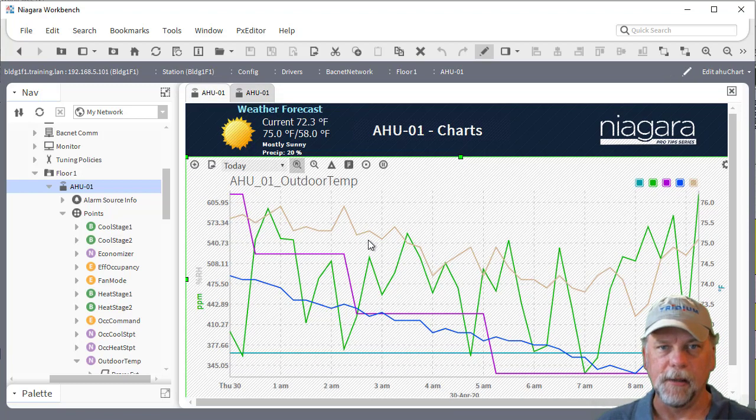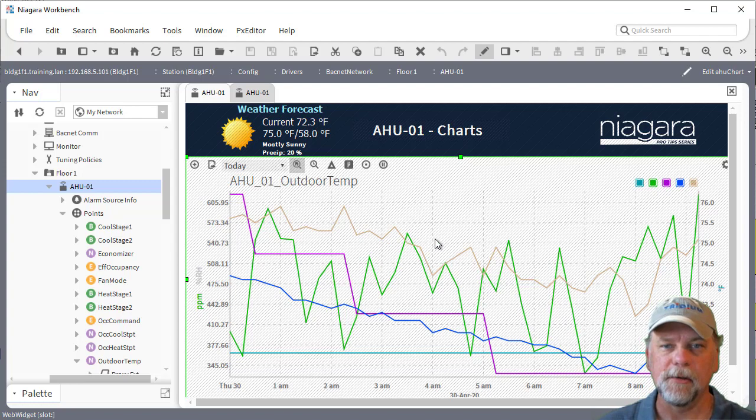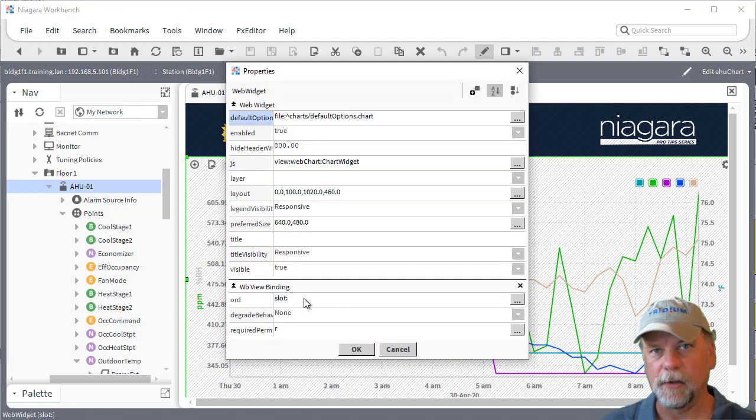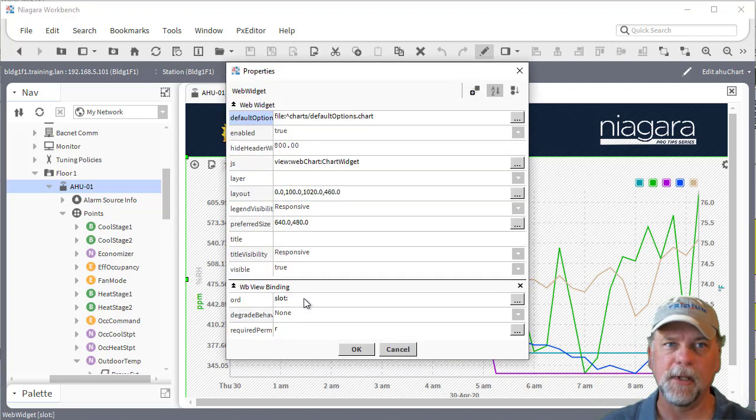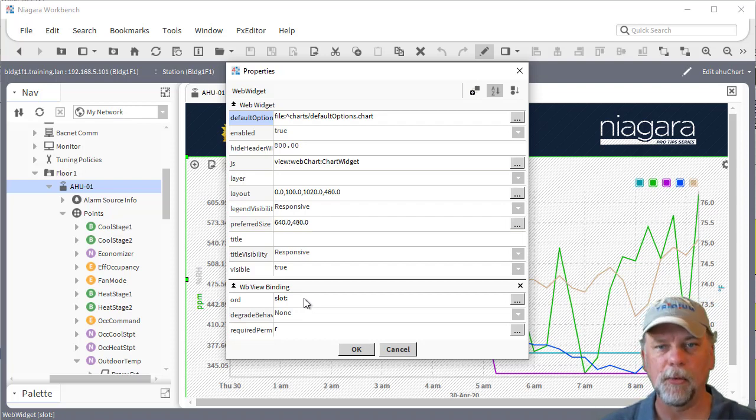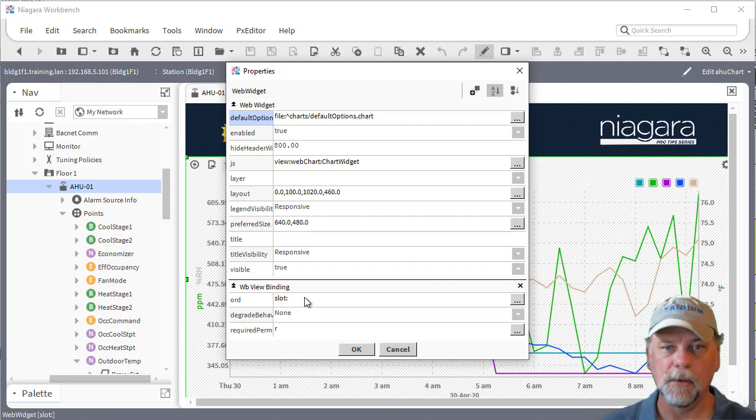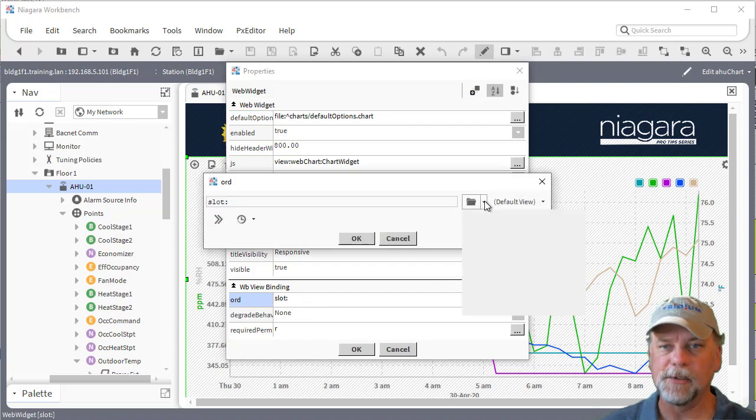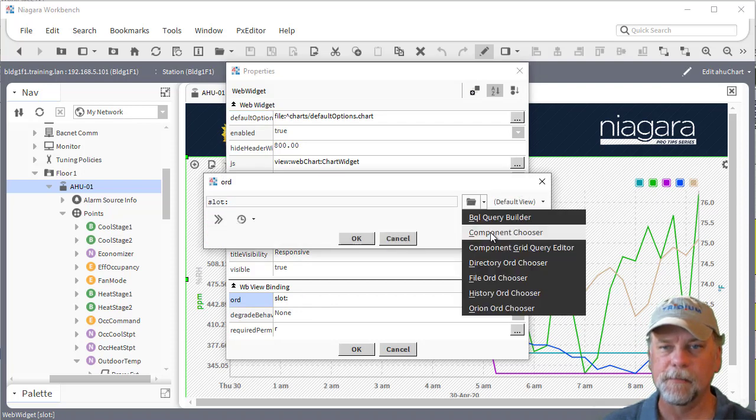In the PX graphic then what we can do is instead of pointing the WB view binding to slot colon or something like slot colon point slash room temp or whatever other ORDs I can use the component chooser here.